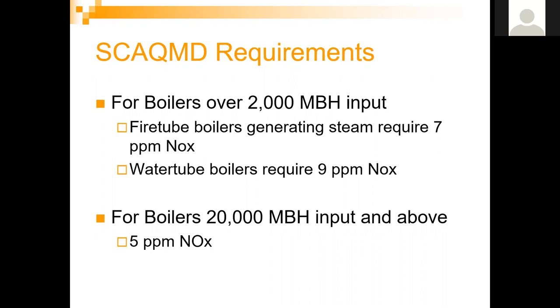Water tube boilers over 2,000 MBH but below 20 million BTUs are still at 9 PPM NOx. For boilers over 20 million BTUs per hour input, the air district now requires sub-5 PPM NOx. We can meet this today even with traditional burner technology if there's a large enough boiler with a large enough furnace — not necessarily requiring an SCR system, though selective catalytic reduction is another option. A guaranteed 5 PPM NOx doesn't leave much room for forgiveness, requiring very precise combustion setup.